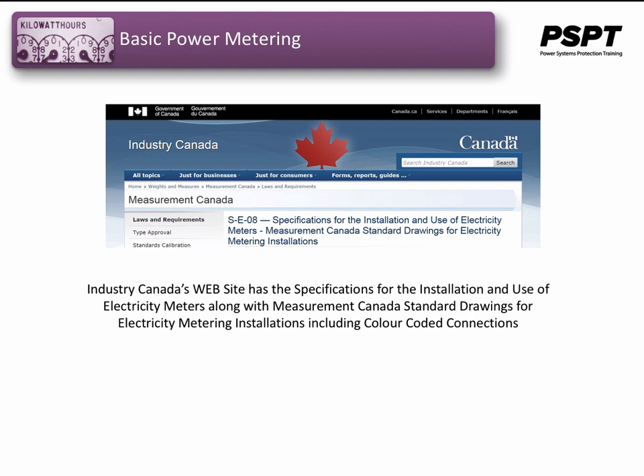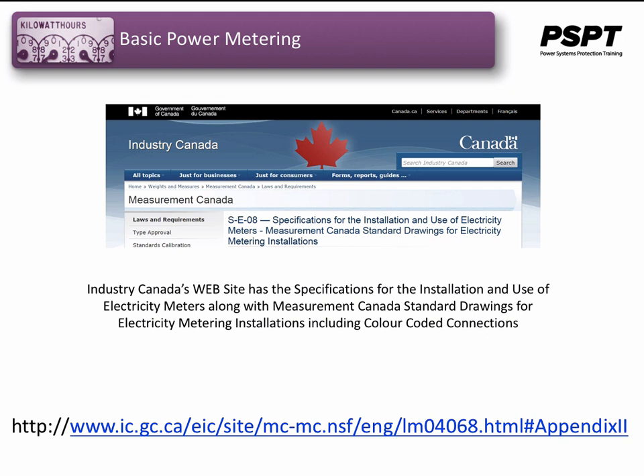So far, we've been sampling excerpts from the Measurement Canada's standard connection diagrams and connections for metering systems, anything from a single phase to a three-phase system, 2-wire, 3-wire, 4-wire systems. They're all listed here on the Government of Canada website. They can be found at this location, and just about every metering system in Ontario and certainly Canada adheres to this standard so that we can continually refer to it and make sure that our connections are correct and are standard.